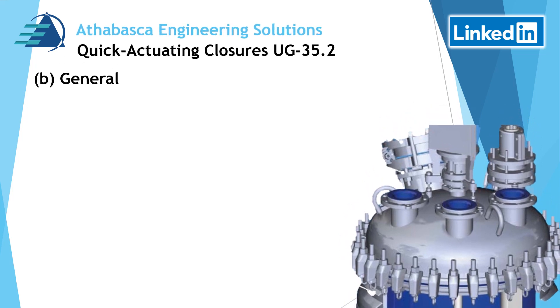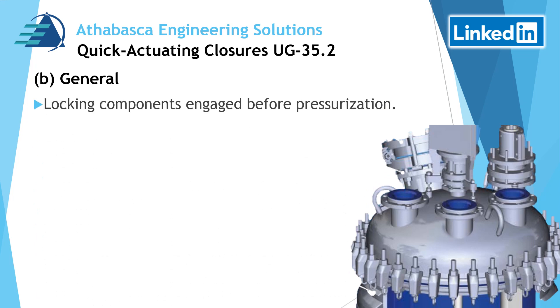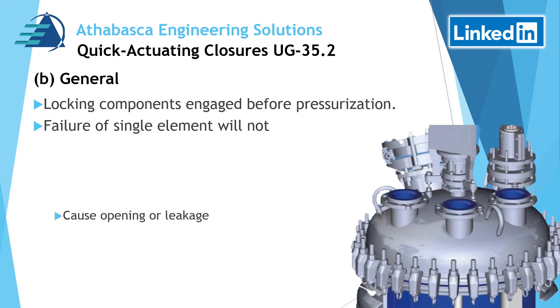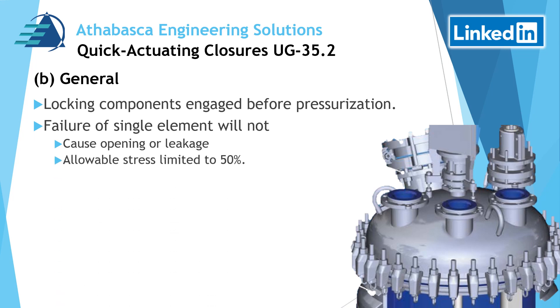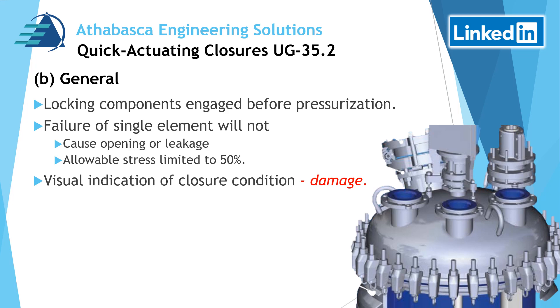In Part B, general requirements: locking components must be engaged before pressurization. Failure of a single element will not cause opening or leakage. The allowable stress cannot exceed 50% in this design — that 50% limit is really to reduce the chance of fatigue. There must be visual indication of the closure condition so you can see any damage, and visual indication of whether it is fully engaged is also a requirement.